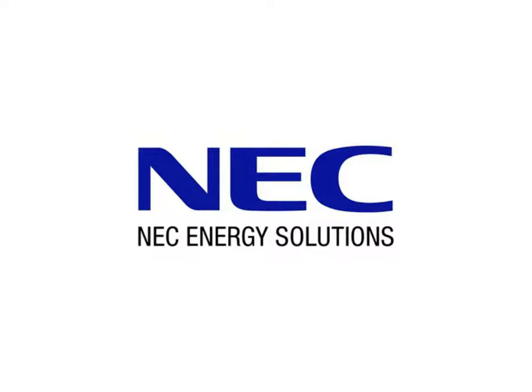For energy storage, since there is something called a benefits factor in the frequency regulation market, energy storage is typically cleared at 3 times the rate of traditional resources. So as PJM looks to each hour of every day, make sure that there's 700 megawatts of some resource out there that it can ramp up and down at its command using its control signal. It'll clear energy storage at 3 times the rate of traditional generation like a coal-fired plant or a gas-fired plant.